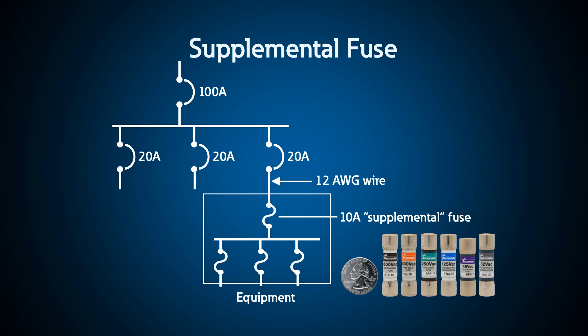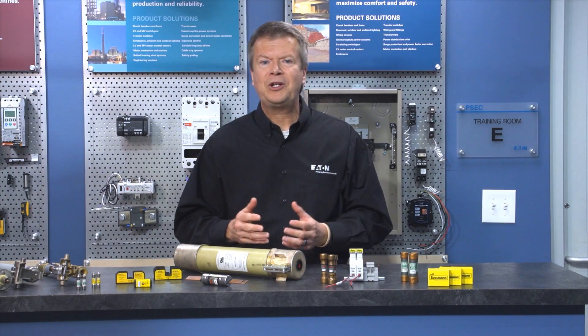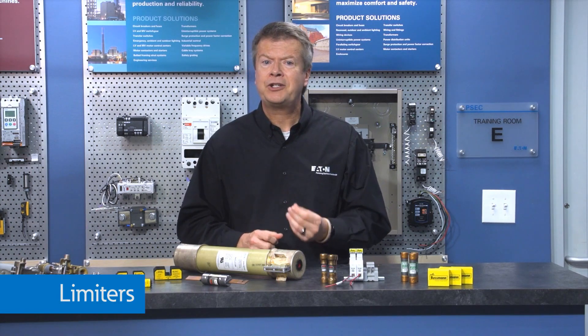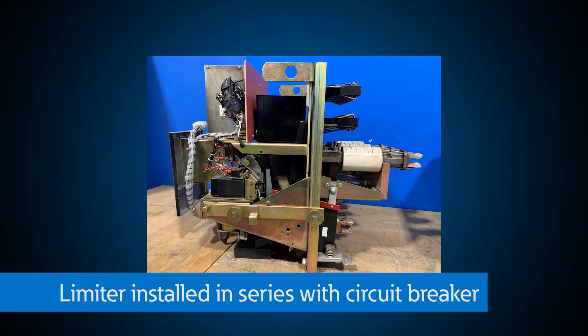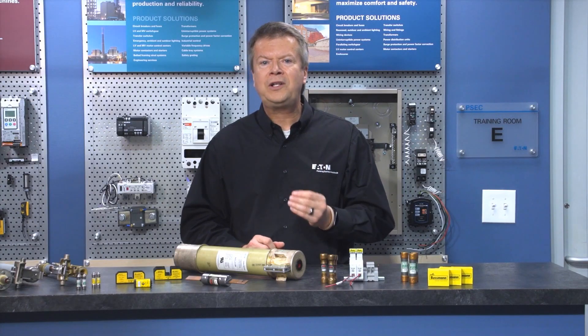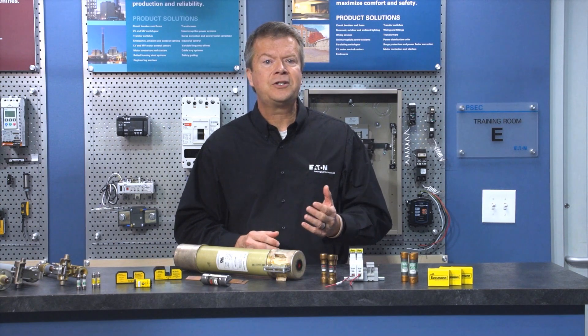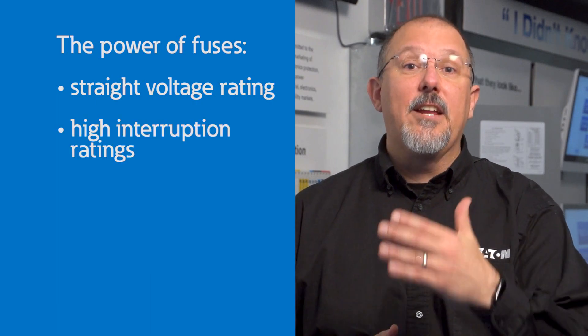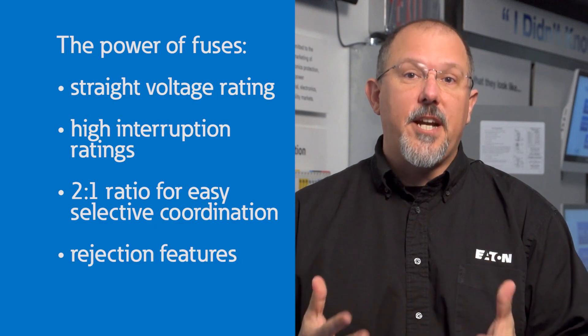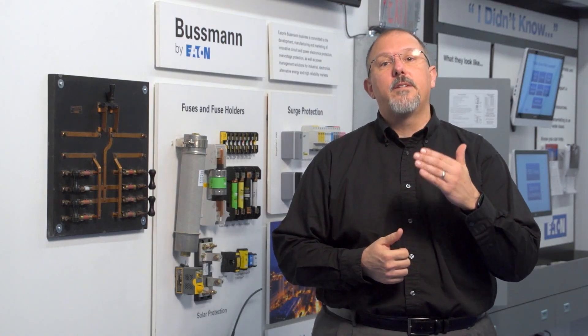Special application fuses include: high-speed fuses for semiconductor applications in VFDs and similar power electronics, sized based on I²t let-through energy; supplemental fuses placed inside equipment as backup for the main protective device; and limiters, connected in series with other OCPDs in low-voltage systems, which only clear very high current faults — effectively increasing the SCCR of that OCPD. The power of the fuse is in its simplicity: straight voltage ratings, high interrupting ratings, 2-to-1 ratio for selective coordination, rejection features, and current limitation.